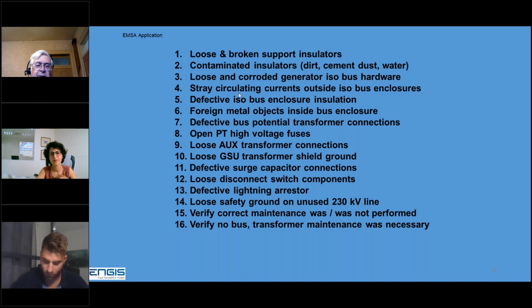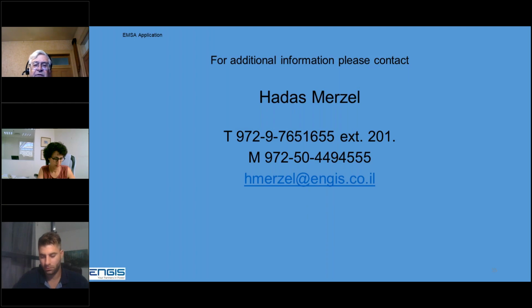Bus conditions, same thing: loosened and cracked and broken insulators, contamination, hardware that's corroded, stray circulating currents outside of the bus enclosures. Some types of isophase bus have a lot of insulation to separate the enclosures. That goes bad with time. Foreign metal objects, we found chain falls on the inside. We found solvent cans on the inside of bus. Potential transformer connections are very common on the PT. High voltage fuses will open up, and transformer problems.